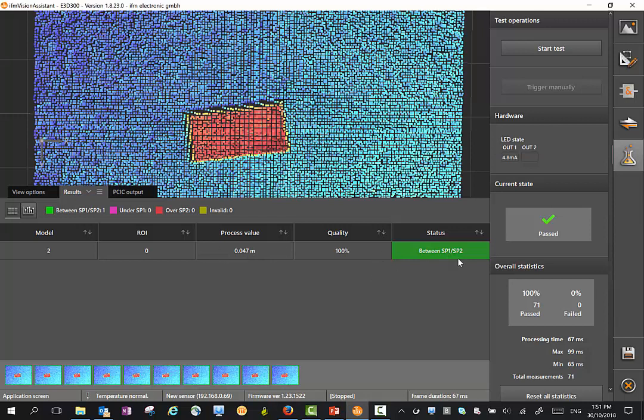I hope that gives a bit of an idea of the setting of the 3D sensor. You also see here with the analog output, it actually displays the analog output in a milliamp value. Because we set it between 0 and 1 meter, the actual value in milliamps is 4.8 milliamps.